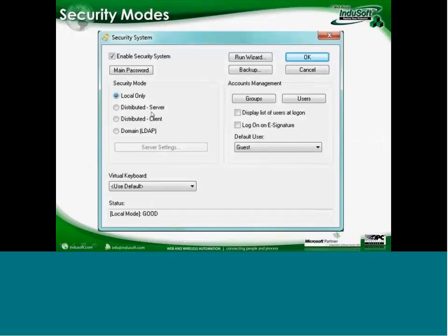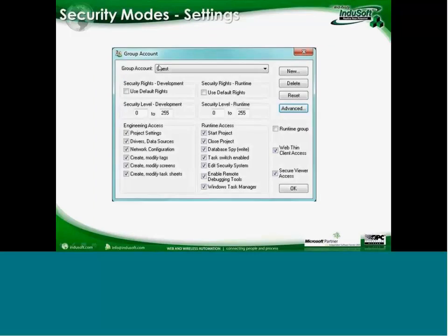When setting up the security system, you choose one of those modes, then set up groups and users. When you set up groups, you get a dialog where you can choose the development and engineering environment assignments — whether they can save settings in the development environment — and then what they can do in the runtime environment. Typically you'll see groups like operators, supervisors, engineers or developers, and maintenance people with different access rights.